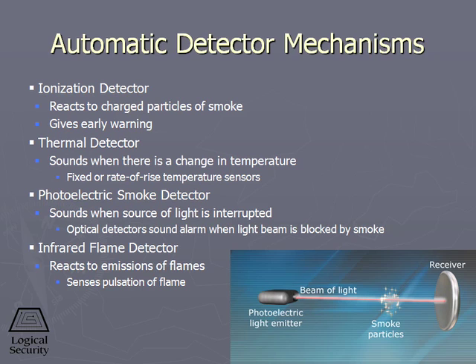The next one is called the photoelectric smoke detector. What this guy has is a light source that hits a photo detector. And when the smoke in the room fills to a point where it breaks that light beam, it sounds the alarm. And the fourth and final is the infrared detector. Now the infrared detector also uses a photoelectric cell to identify light, but it doesn't provide its own light source. The light source that the infrared flame detector is looking for is the actual fire itself, the heat from the fire itself. You should know all four of these types of fire detectors.